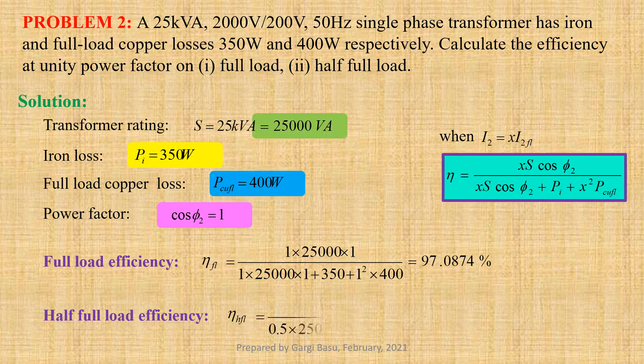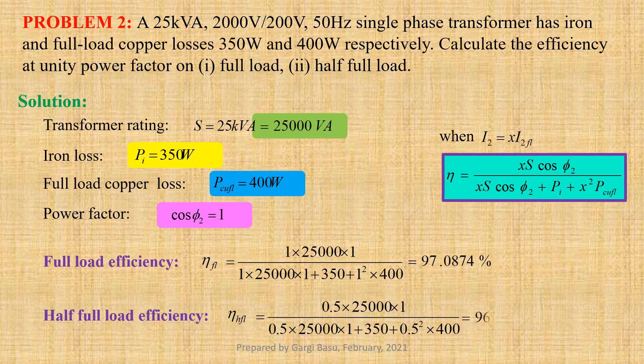Half load efficiency: ETA at 0.5 load equals to 0.5 into 25,000 into 1 divided by 0.5 into 25,000 into 1 plus 350 plus 0.5 squared into 400, that gives us 96.5251 percent.